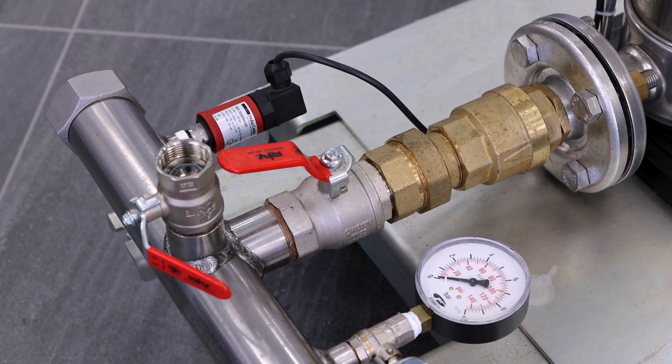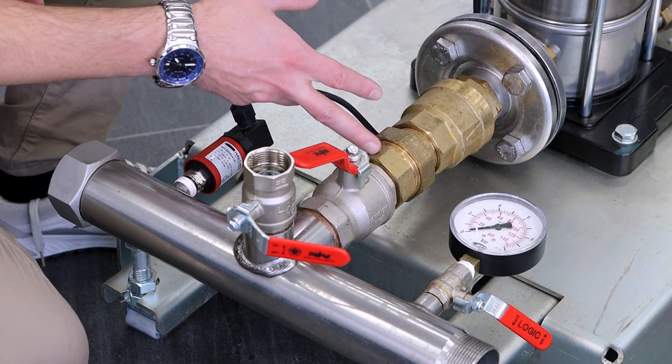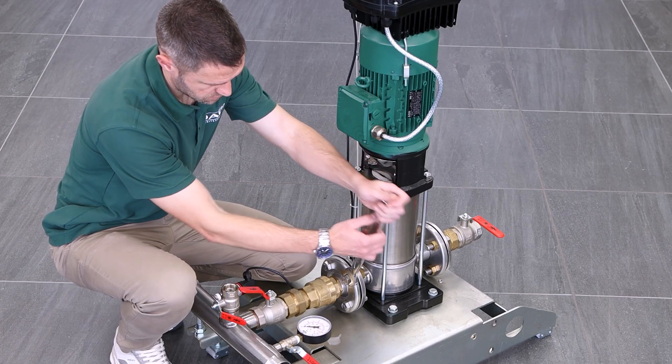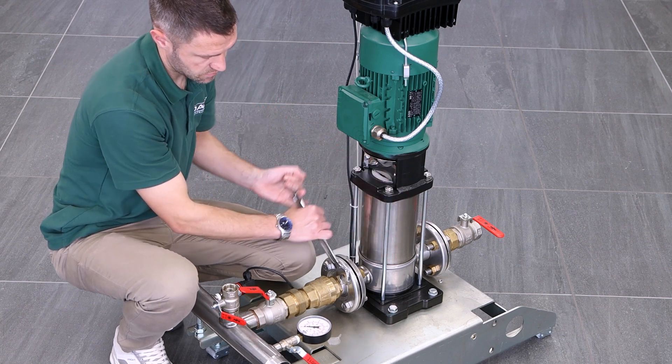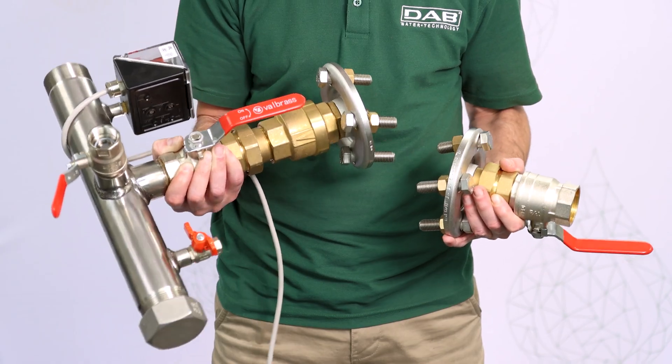On a traditional booster set, like this one, you need to install the no-return valve on the outlet pipeline, and when inspecting it, we need to remove the flanges, undo the pipeline, extract the valve for inspection, then apply the sealing tape again. That would take about half an hour or so.